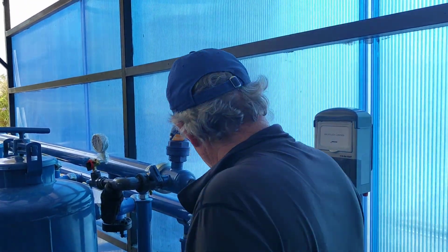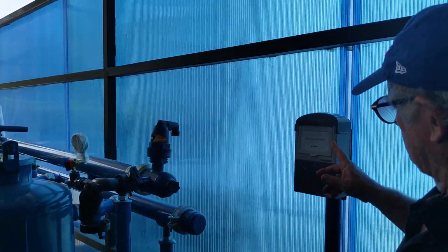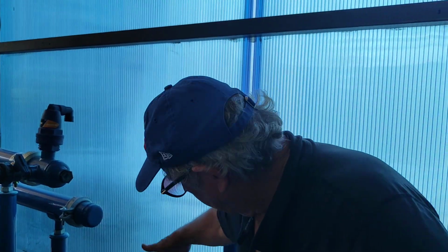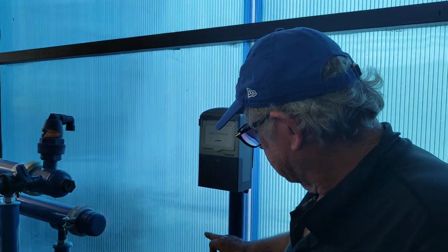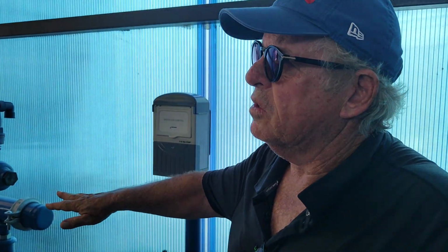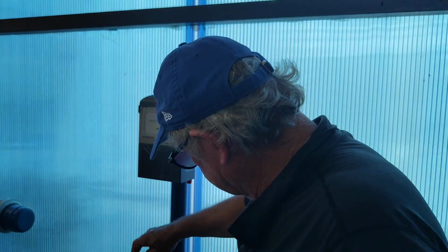Hydraulic order. So the solenoid changes electrical order to hydraulic order. I'm bringing water to here and I take it from here, and once it changes position by this control, then I can control the valves hydraulically. These valves usually we control hydraulically. There are also valves, you will see later on, that have their own solenoid, so I can order electrical and not hydraulic. But anyway, we cannot use this one without it.